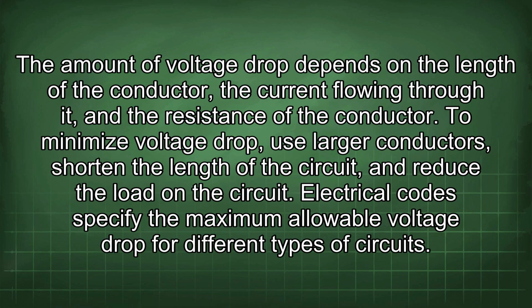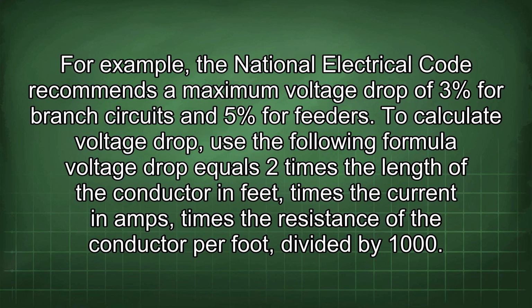The amount of voltage drop depends on the length of the conductor, the current flowing through it, and the resistance of the conductor. To minimize voltage drop, use larger conductors, shorten the length of the circuit, and reduce the load on the circuit. Electrical codes specify the maximum allowable voltage drop for different types of circuits. For example, the National Electrical Code recommends a maximum voltage drop of 3% for branch circuits and 5% for feeders.